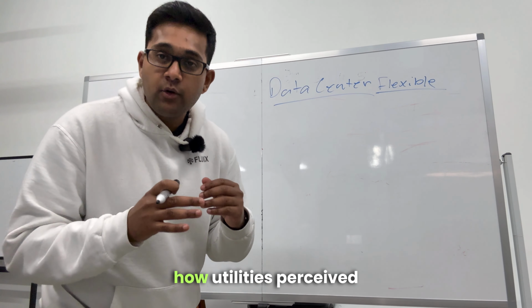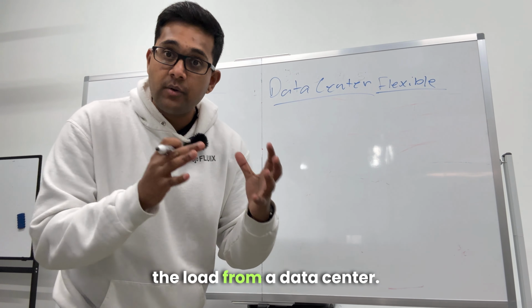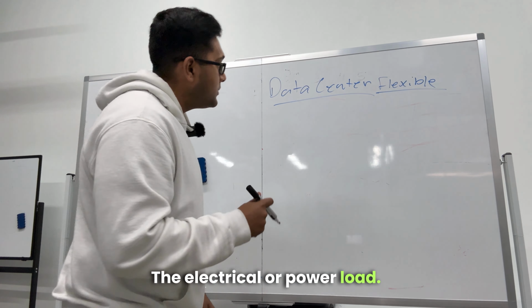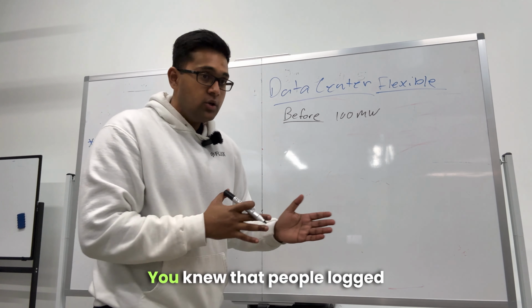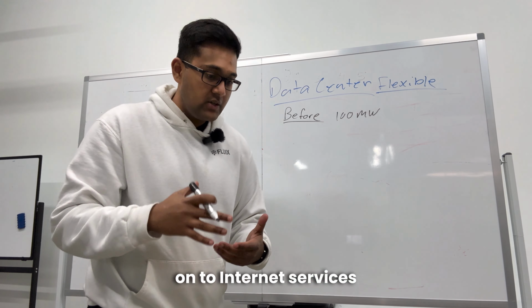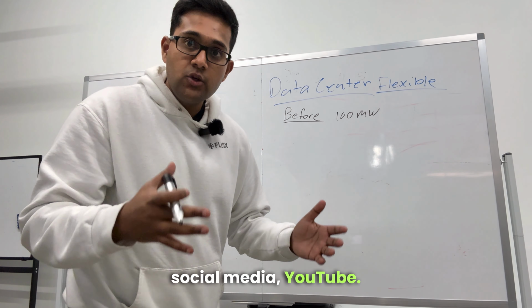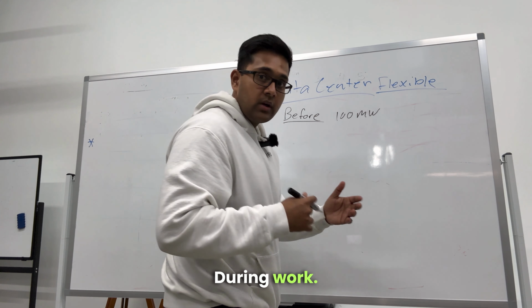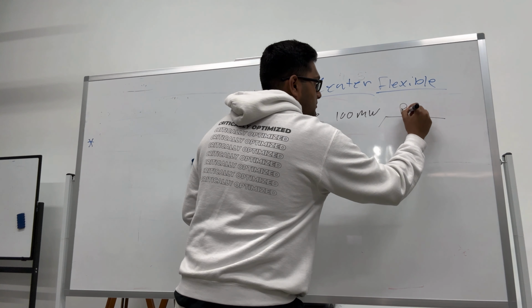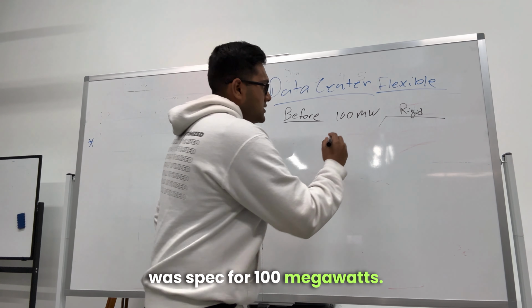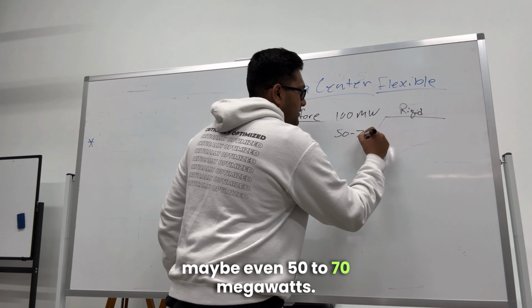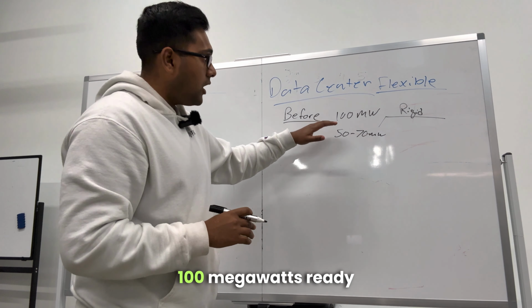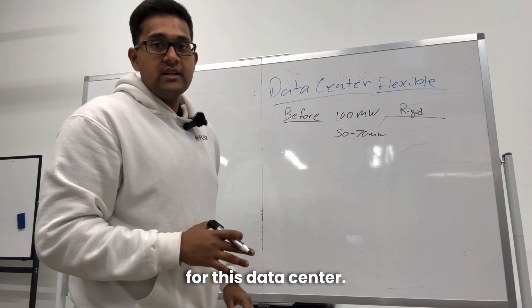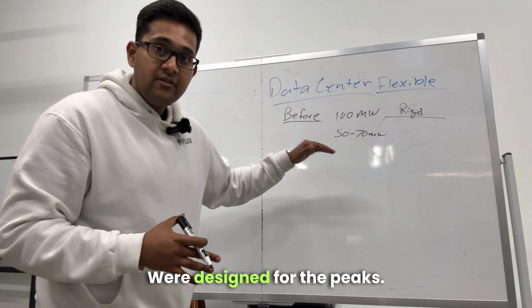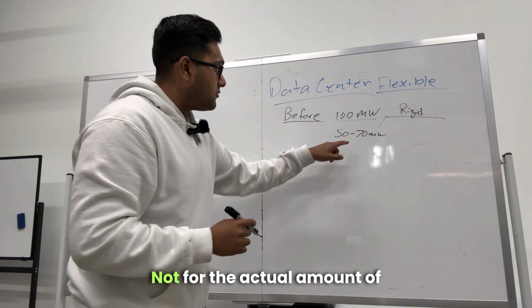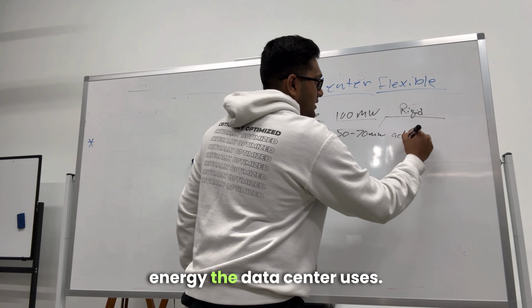We got to understand how utilities perceive the load from a data center. Data center load was pretty predictable. You knew people logged on to internet services like Instagram, Google, YouTube when they wake up or during work, so the load profile was pretty rigid. Even though a data center was spec'd for 100 megawatts, it would probably only use maybe 50 to 70 megawatts. The utility would have 100 megawatts ready 24/7 because they were designed for the peaks, not for the actual amount of energy used.